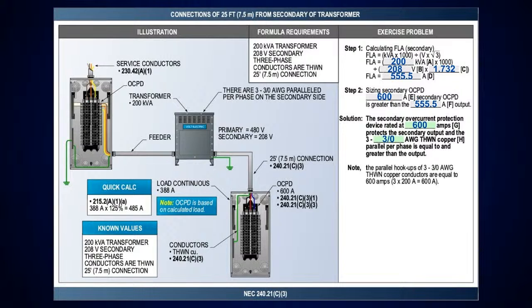Like this one here, this is 25 foot. I do the same calculation. I've got a 200 kVA transformer. I'll multiply it by 1,000. It's a 208 volt secondary here with 3 phase, so I multiply it by 1.732. Do my calculation. The full load amperage is 555 point something amps. The next size above that is a 600 amp overcurrent device. Now I'm going to parallel this one 3 times.